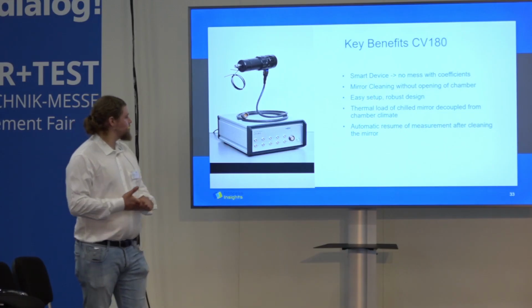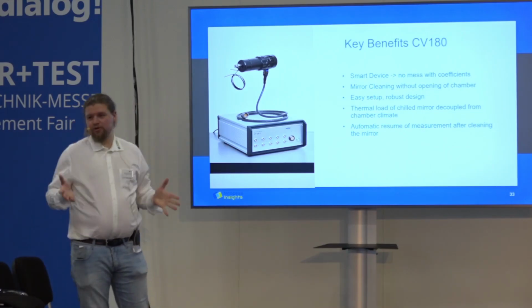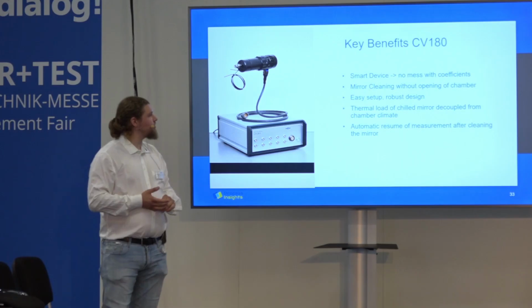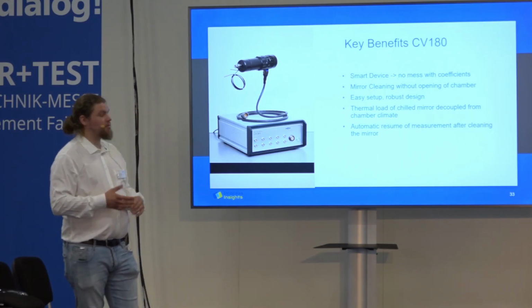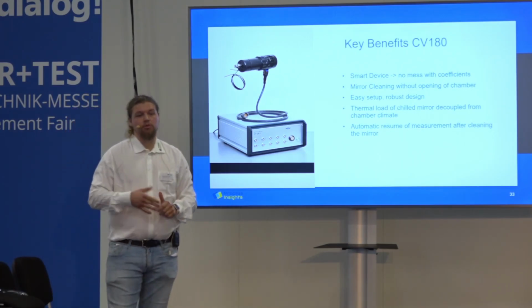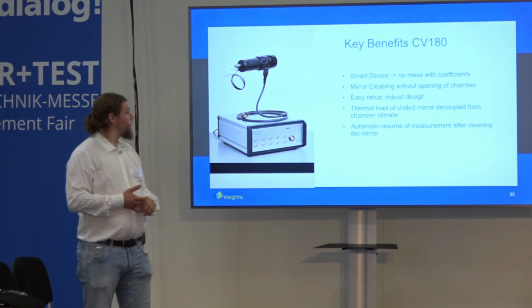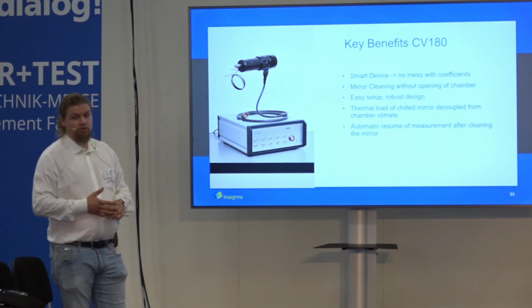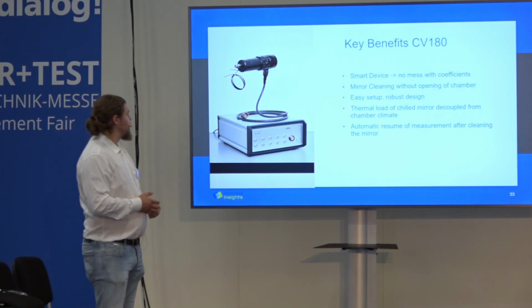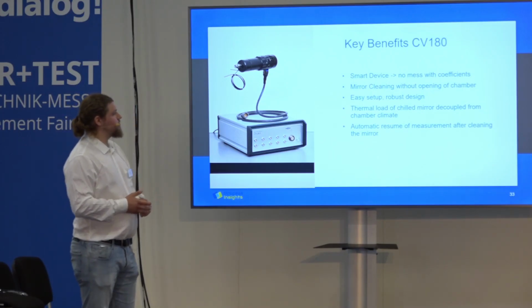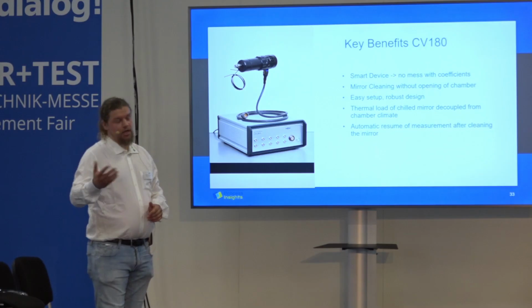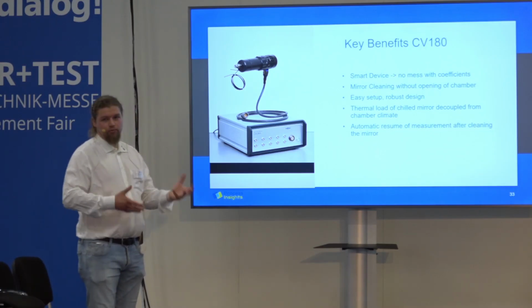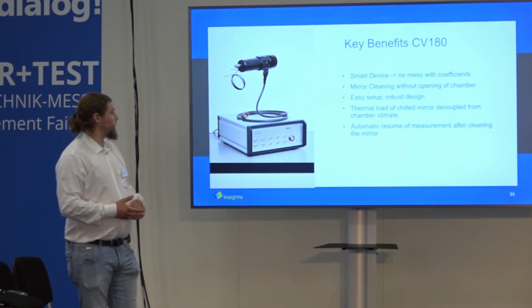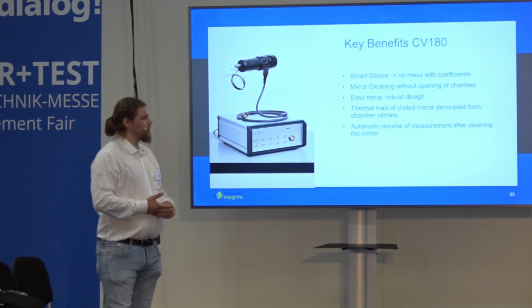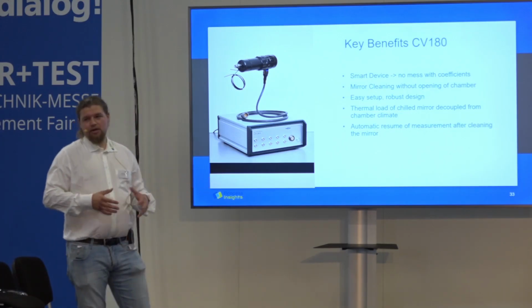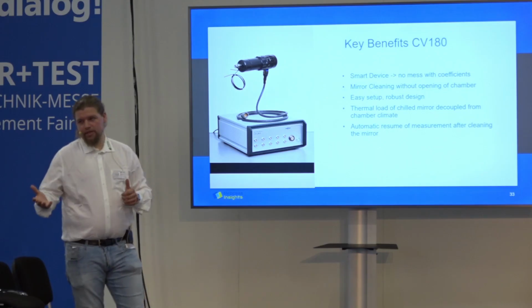So this was an overview of the climate chamber calibration itself. Let's have a look at the key benefits and probable further development opportunities for the users. So there is now a smart device available which will automatically load the coefficients, so you can work fast with this device in climate chambers. You can do the mirror cleaning from the outside, so you don't need to open the chamber.